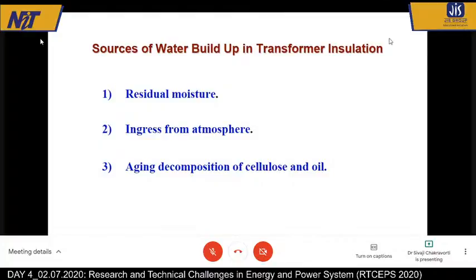Or rather, at the time of installation of the high voltage transformer, the moisture content should be less than 5 ppm in oil and 0.5% by weight in paper. Generally, it is 0.3% by weight. Then there is ingress from the atmosphere. The transformer has a top tank and an oil drain valve, etc. So if the sealing is not good, then moisture will come in, but it is very low because of care.